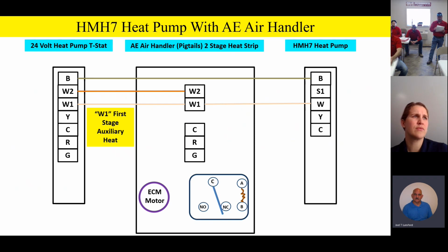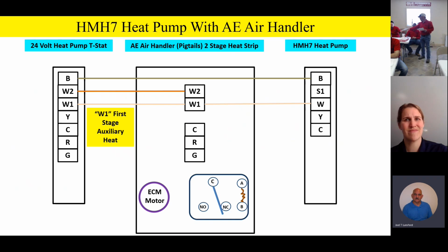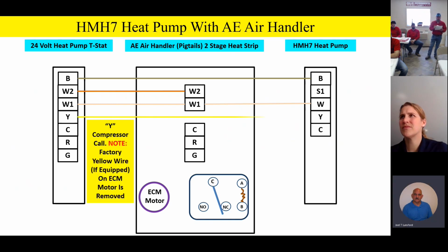Now remember, guys, when you have a heat pump and it goes into the defrost mode, we're going to bring those heat strips on via that W1 on the indoor unit. This is why we have to have that W input from the outdoor unit come in and energize the heat strips during defrost mode of operation. The Y terminal is going to be our compressor call. You'll see that goes from the thermostat outside. That'll be for our compressor call.